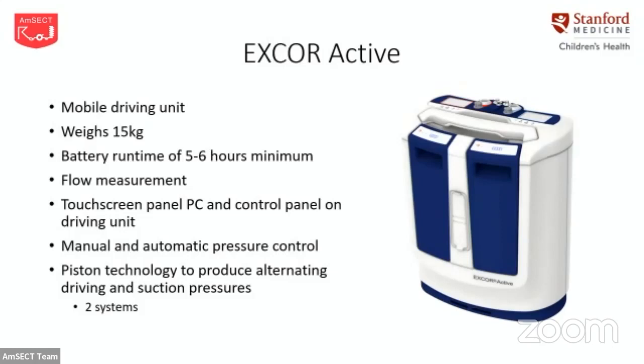So again, with a BiVAD, the first piston will run your LVAD, the second piston will run your RVAD, and if one of those pistons fails, the other piston will have to pick up the work of both VADs, and it's going to alternate between the 2 every 2 pump cycles, but that's an emergency, like a driver change out, situation.